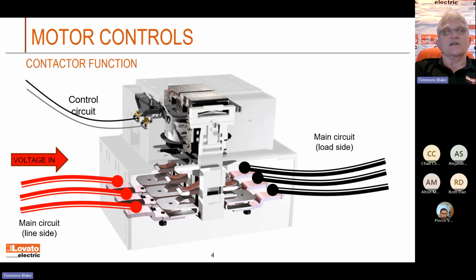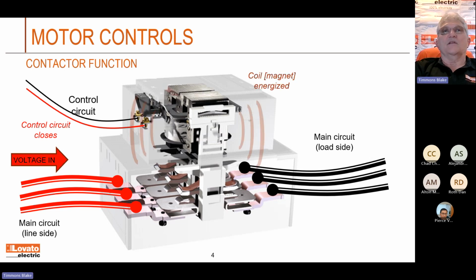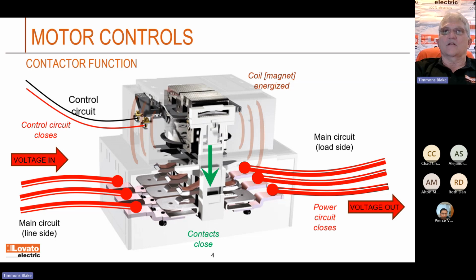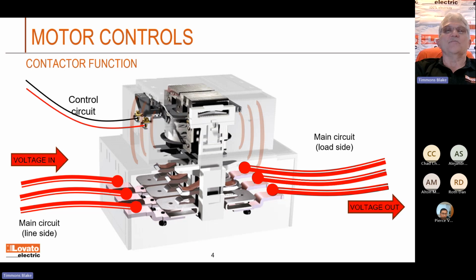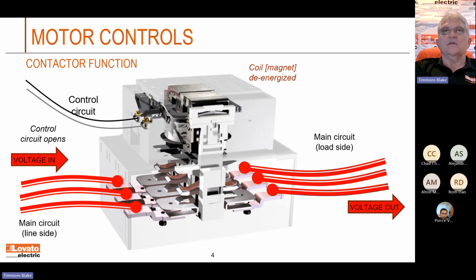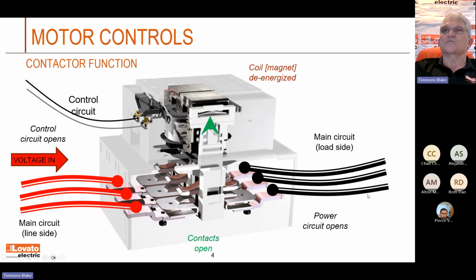And then you're going to have the coil. We say coil here in Texas. And when you energize that coil, you'll energize the magnet around the armature. There's a little armature that works back and forth in there. When you do that, it'll close those contacts and apply power out. Then as you remove power from that coil circuit, it'll drop out the magnetic coil and de-energize. Of course, you'll get a little bit of an arc, and then you'll lose power to the motor side. Well, that's pretty much how you control a motor.